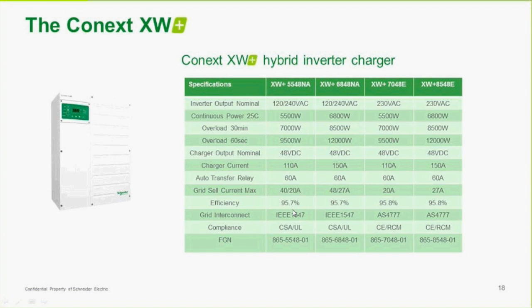Here are a few of the specifications for the XW Plus. And as you can see, it has a very, very high overloadability. This particular inverter is very robust and can be used for starting large loads. And it's a transformer-based inverter, which gives us this capability. So as you can see, you can overload it substantially for the time it takes to start a pump or a motor on an electric saw or some other device that has a current draw, and it'll handle it.